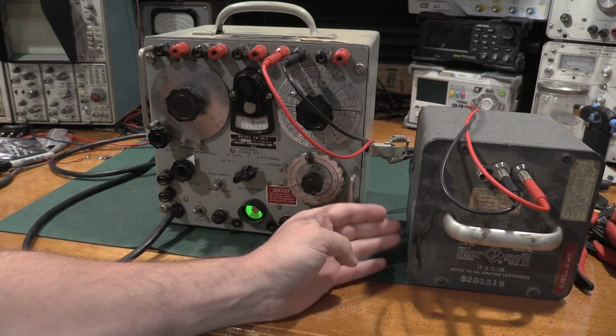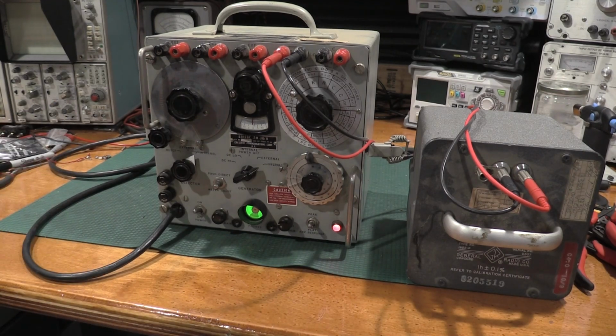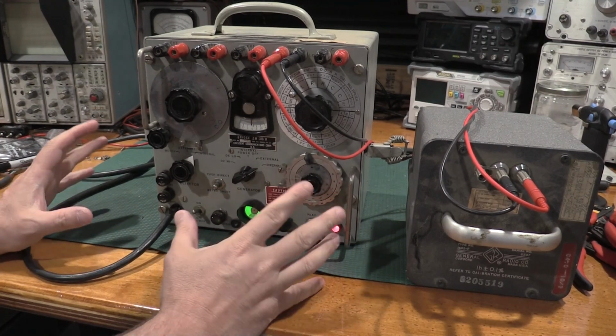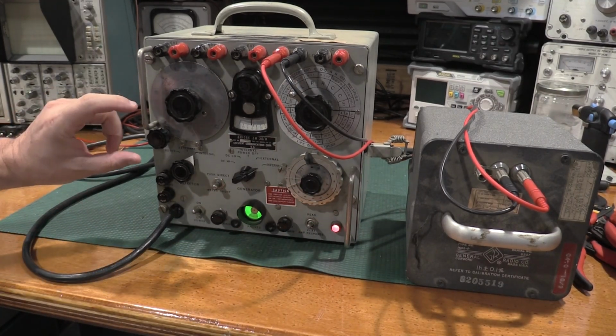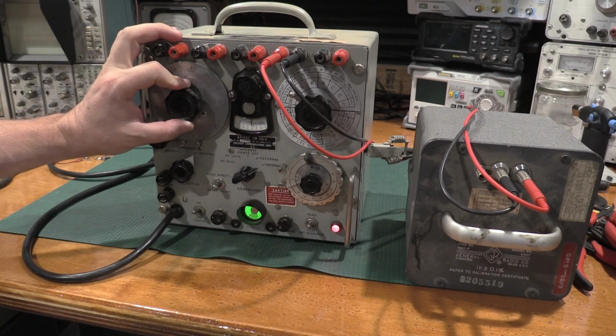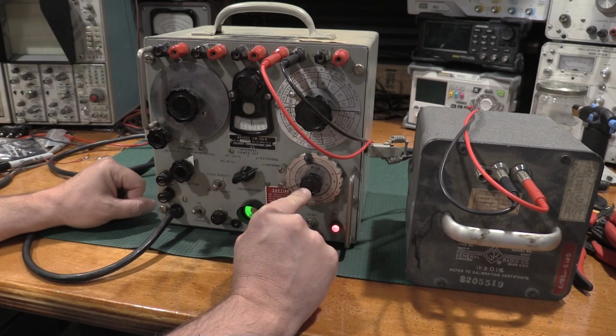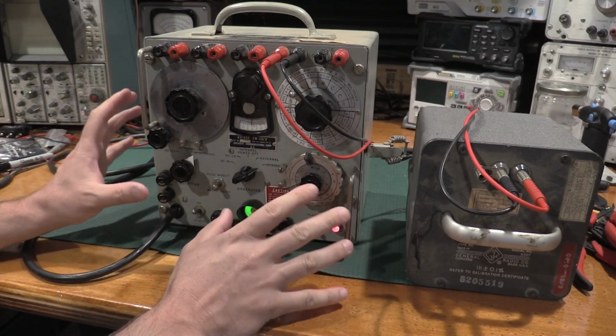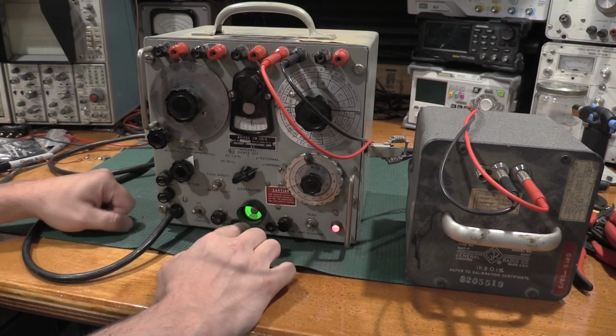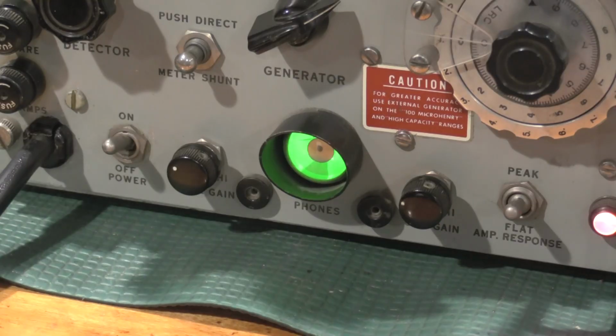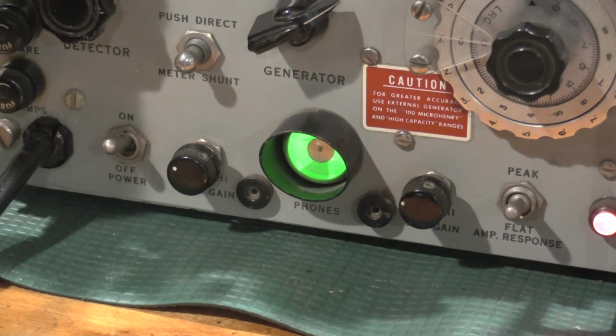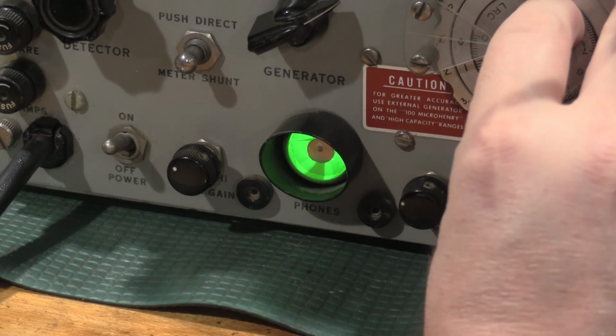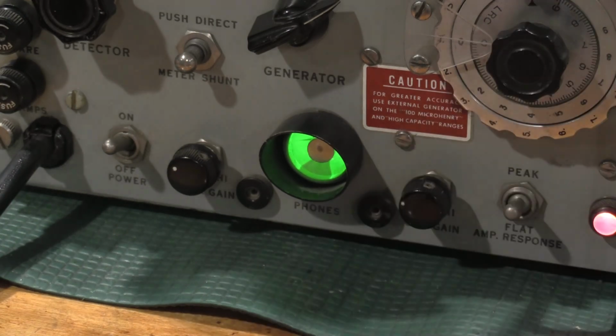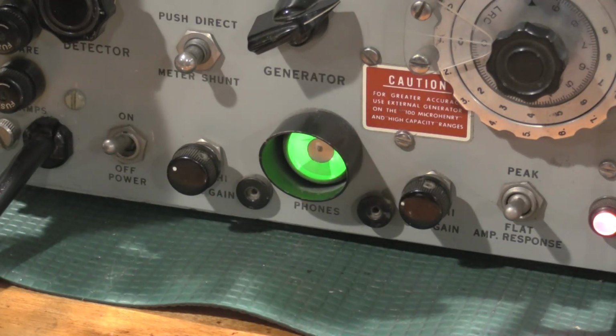Checking the inductance with my random 1 Henry inductance standard. This is a little trickier with this unit because you have to adjust the dissipation Q dial at the same time you're adjusting the RLC dial, and then you're adjusting both. You're kind of playing with both at the same time. This is coarse adjustment, fine adjustment for maximum shadow. So if I turn the Q dial, the shadow opens and closes, and I'm looking for maximum open. If I turn the RLC dial, it's very sensitive, so we have a nice null. So that would be right where we'd take the measurement.